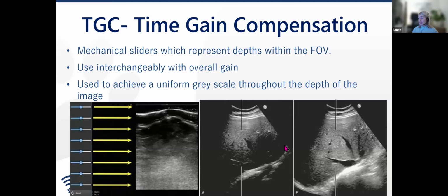Okay, so if we look here at this bit of liver, this is with the TGC set straight down the middle. We can see that we've got quite a nice bright near field of that liver. However, this far field is quite dark, okay? And that's because these echoes down here are having to travel further than these up here. So they need a little bit of extra oomph. And that's where your TGC comes in. So if we take the bottom 2 or 3 or even 4 of them to the right-hand side, we'll get that even grayscale throughout the depth of the image.